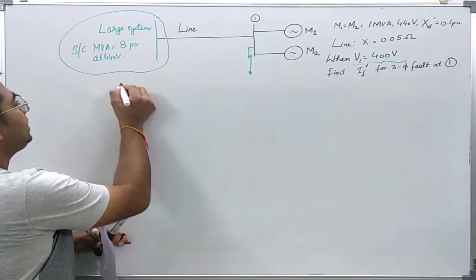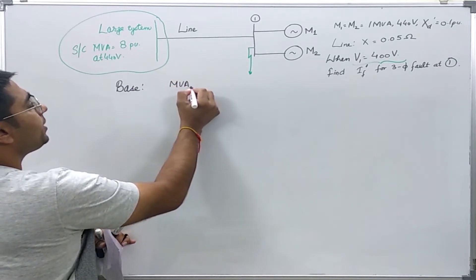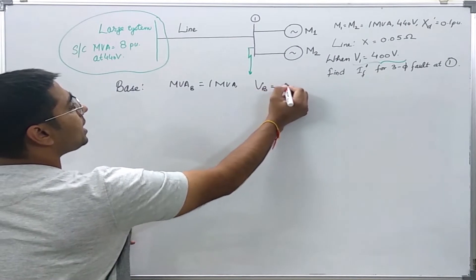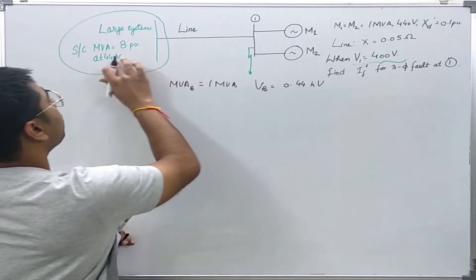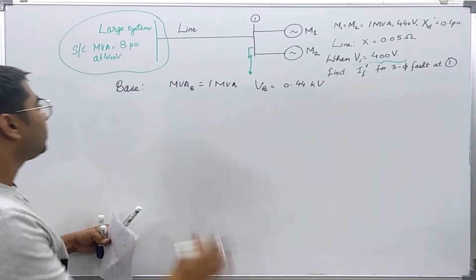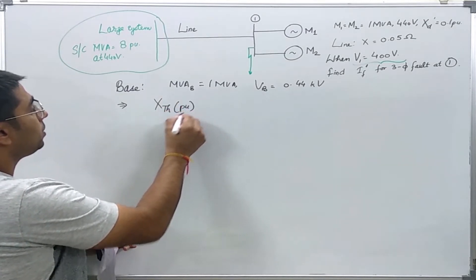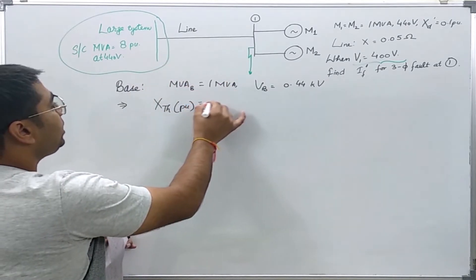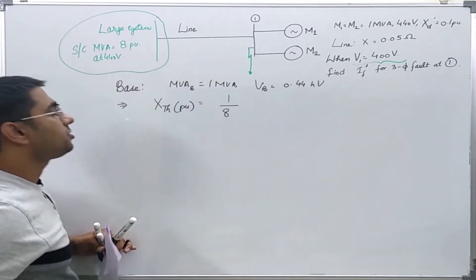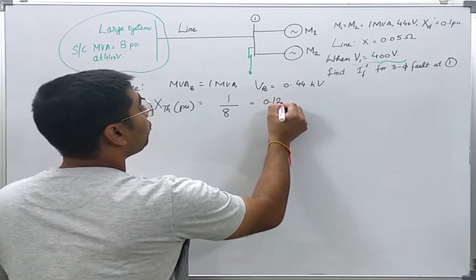We assume base values: MVA base is 1 MVA and voltage base is 0.44 kV (440 V). With the same base voltage as given for the power system, the Thevenin reactance in per unit is simply 1 over 8, which comes out to be 0.125 per unit.